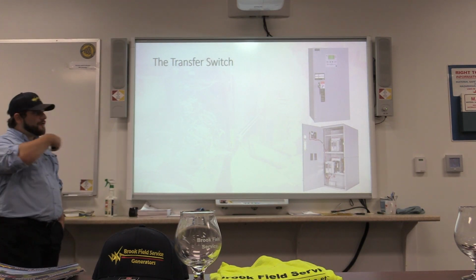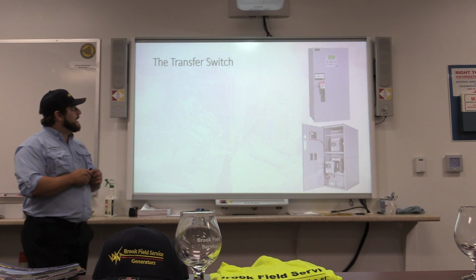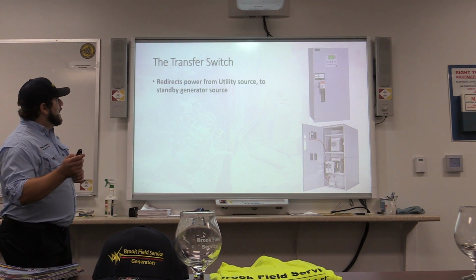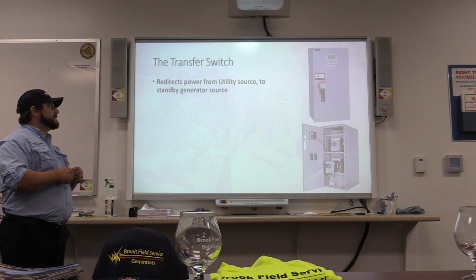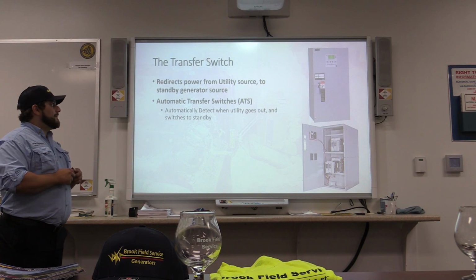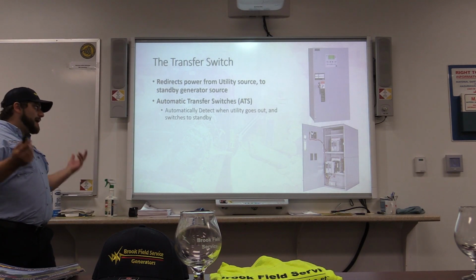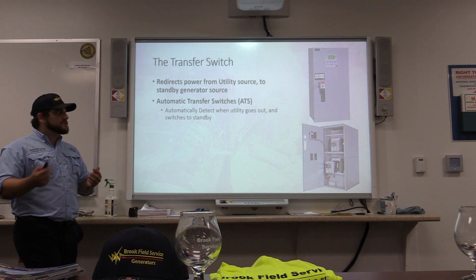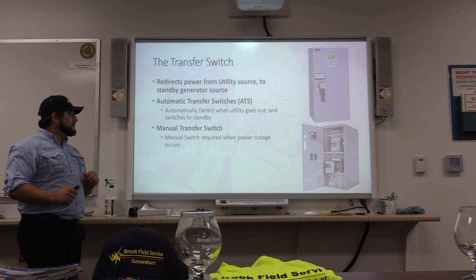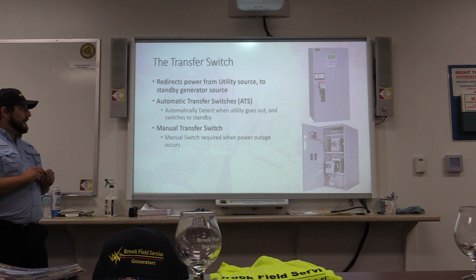But the third most important part, as I was talking about, is that transfer switch. Again, it redirects power from the utility source to the standby generator source. Automatic transfer switches automatically detect when the utility goes out and switch to standby. As you can imagine, manual transfer switches require someone to act when a power outage occurs.